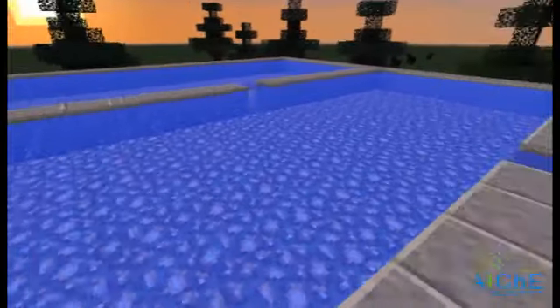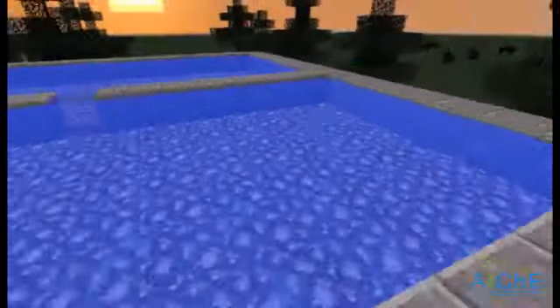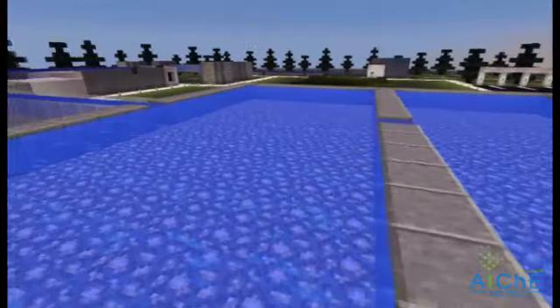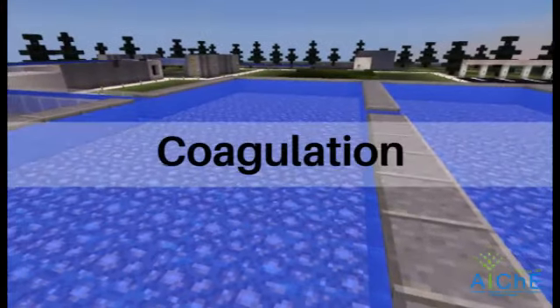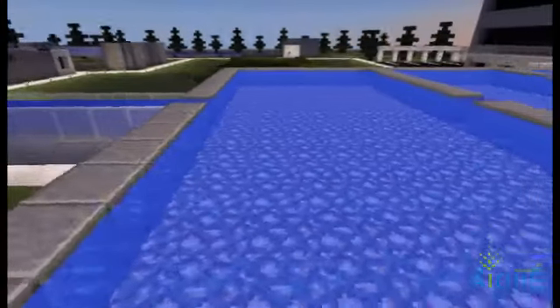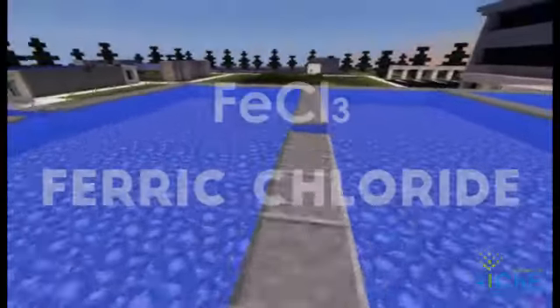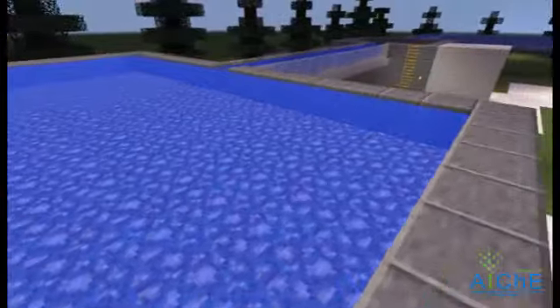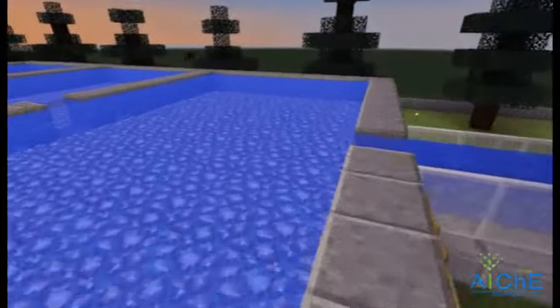Pre-alkalinization: after adding chlorine, it is necessary to adjust the pH for the following treatment stages, using whitewash or lime. Coagulation occurs with the addition of aluminum sulfate, ferric chloride, or another coagulant, followed by thorough stirring of the water.